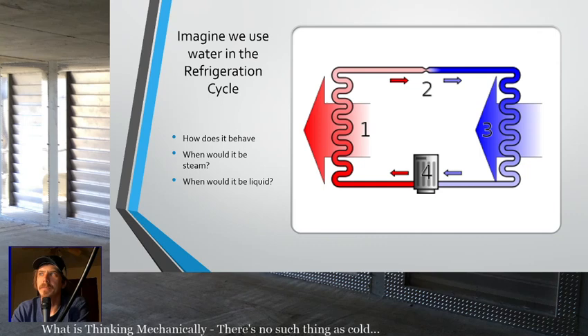And since the temperature drops so fast by lowering the pressure - because that's the other thing happening, we're lowering the pressure at the metering device since we lowered the pressure of that water really quick and turned it into a mist - it's going to pick up heat from the inside, and that heat from the inside is going to turn it into steam again. And that steam goes back to the compressor to be compressed so the pressure goes up and the temperature goes up, so we can give off heat to the outside again.